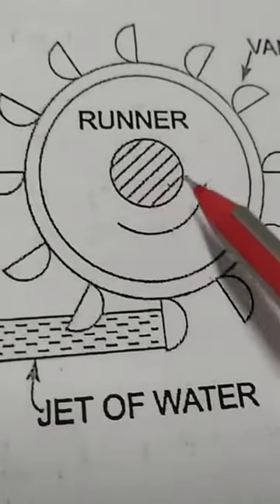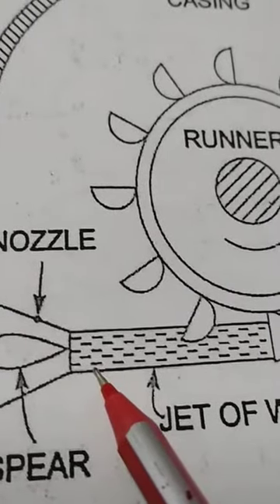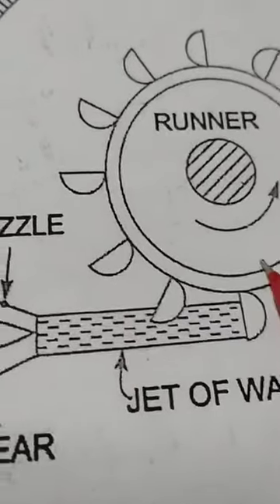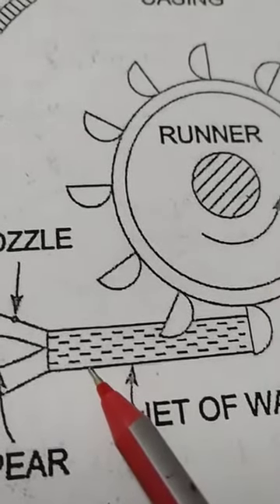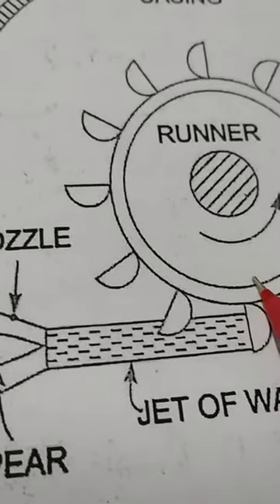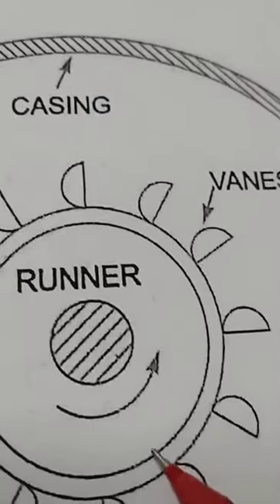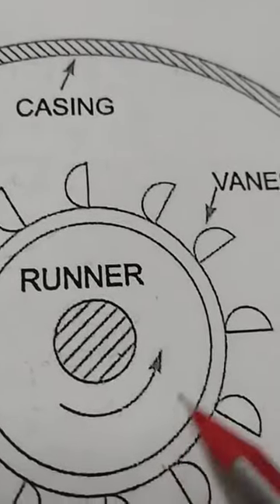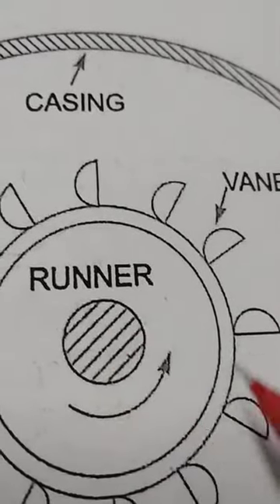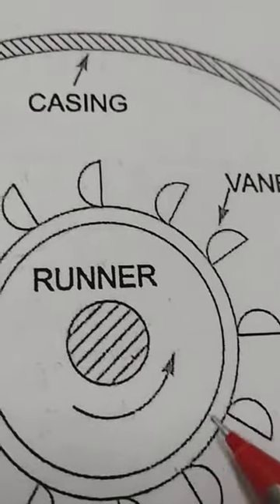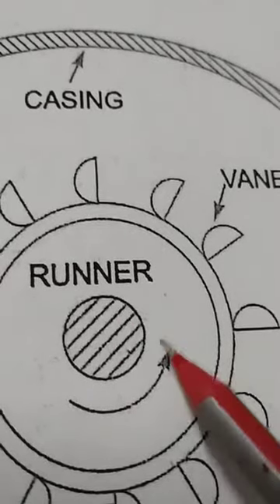Now I will explain the three efficiencies one by one. The first is hydraulic efficiency: water power is converted to runner power. The first is always input and the second is output. The ratio of runner power to water power is called hydraulic efficiency. For mechanical efficiency, the ratio of shaft power to runner power — shaft power is output, runner power is input — is called mechanical efficiency.